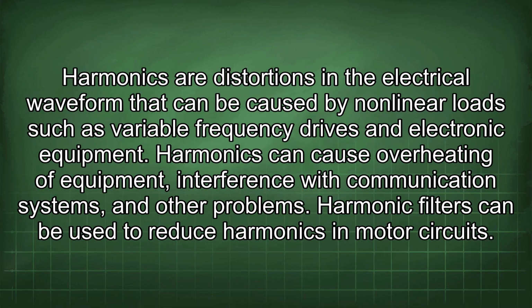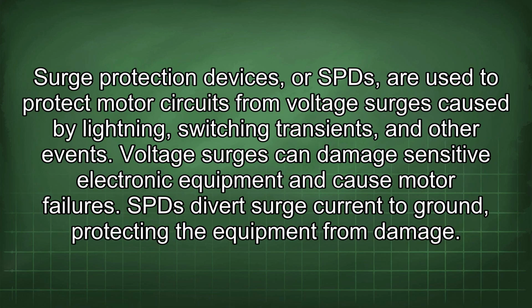Harmonics are distortions in the electrical waveform that can be caused by nonlinear loads such as variable frequency drives and electronic equipment. Harmonics can cause overheating of equipment, interference with communication systems, and other problems. Harmonic filters can be used to reduce harmonics in motor circuits. Surge protection devices, or SPDs, are used to protect motor circuits from voltage surges caused by lightning, switching transients, and other events. Voltage surges can damage sensitive electronic equipment and cause motor failures. An SPD diverts surge current to ground, protecting the equipment from damage.